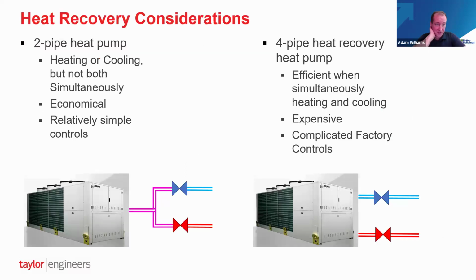Next slide. So the final thing to think about with heat pumps is you can get units as a 2-pipe unit or a 4-pipe unit. The 2-pipe units can do heating or cooling, but they can't do both simultaneously. They have changeover valving so that they can provide heating or cooling, but not both. These are generally more economical and cheaper, and they have generally more simple controls, at least the factory controls, because they're doing one or the other.